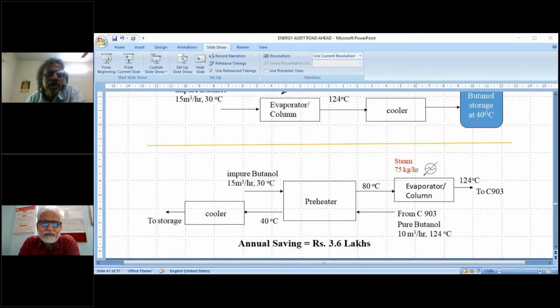We can put a plate heat exchanger and get maybe 40-degree water. Even with a 50-degree stream, we can get to 40-45 degree water with a plate heat exchanger. But many of these textile people use firewood as a low-cost fuel, so it may not be economical. Suppose they're using coal or oil, then it becomes economical - you can put that and recover it. Even 1 degree saving is quite substantial.